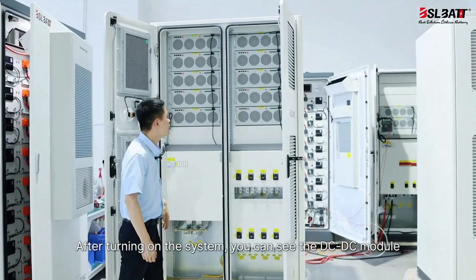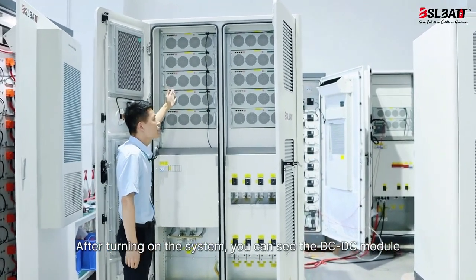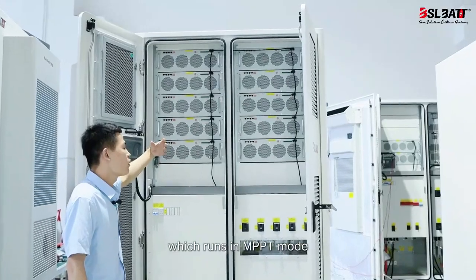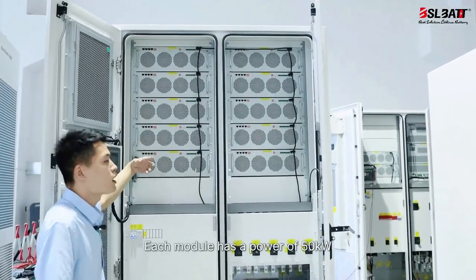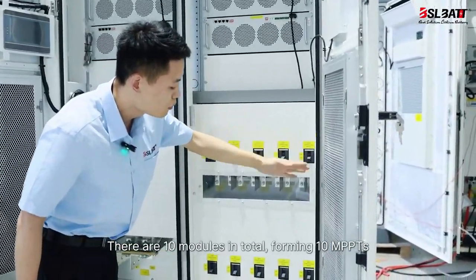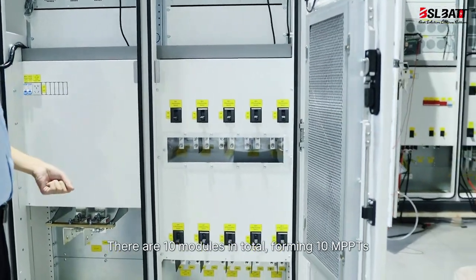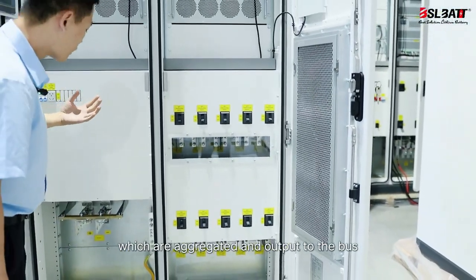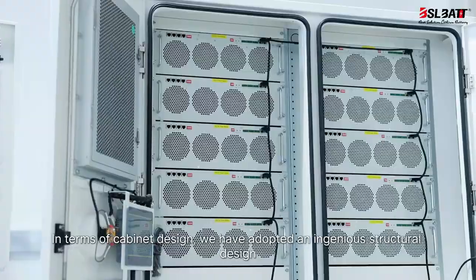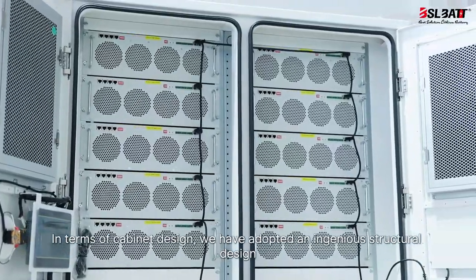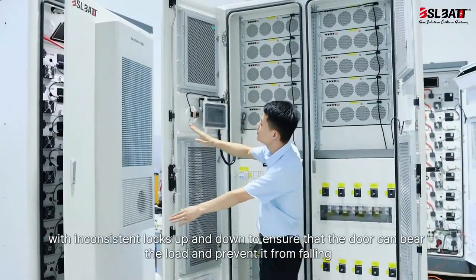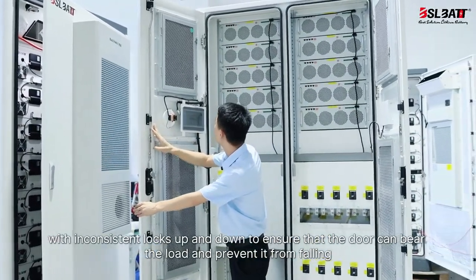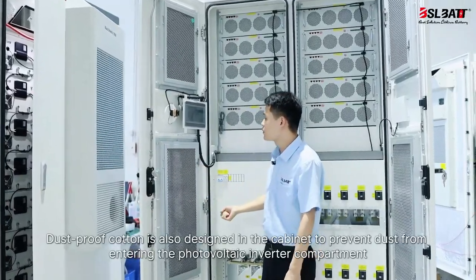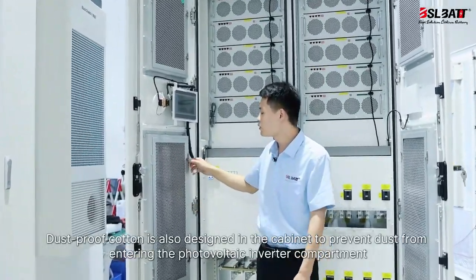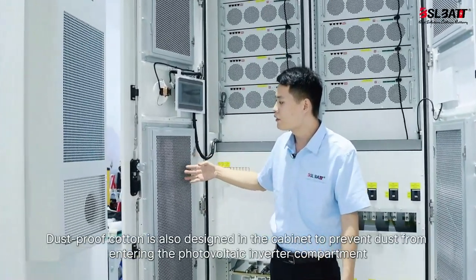After turning on the system, you can see the DC-DC module, which runs in MPPT mode. Each module has a power of 50 kilowatts. There are 10 modules in total, forming 10 MPPTs, which are aggregated and output to the bus. In terms of cabinet design, we have adopted an ingenious structural design, with inconsistent locks up and down to ensure that the door can bear the load and prevent it from falling. Dust-proof cotton is also designed in the cabinet to prevent dust from entering the photovoltaic inverter compartment.